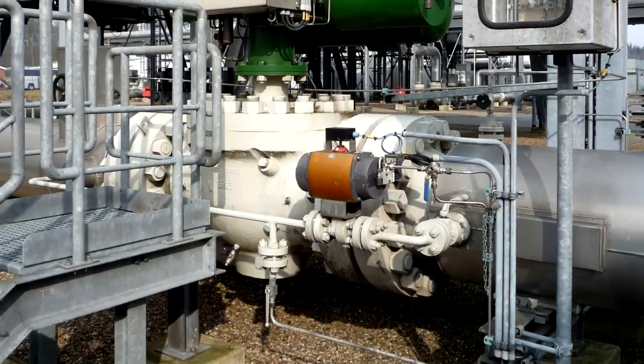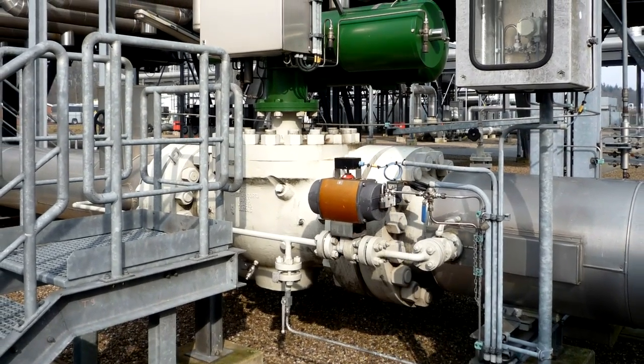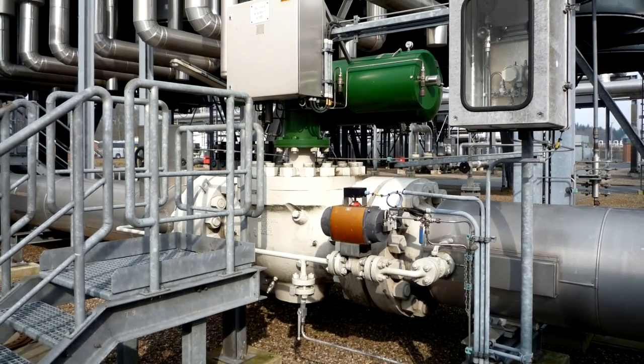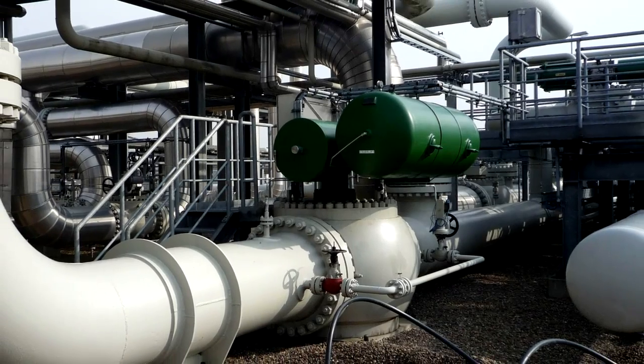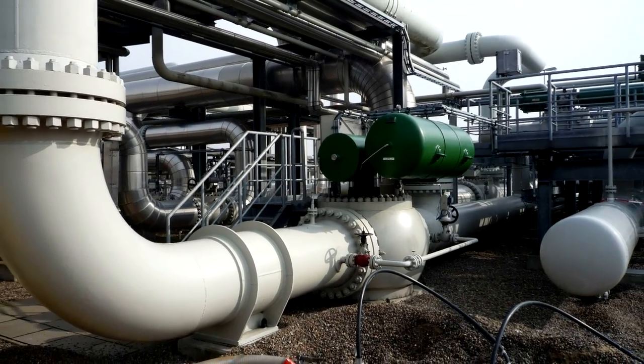As mentioned, over 100 ball valves, most of them operated by air pressure. In storage vessels we have compressed air so that you can open and close the valves at least two times within up to 40 seconds. The system is checked monthly, and we check frequently the functionality and operability of these ball valves.